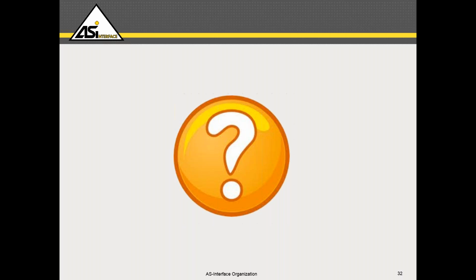Hey John, this is Yen Lee again, I'll take that question. That's really the beauty of the ASI system, right? As a machine builder, you can standardize on your I/O platform no matter if the customer specifies a Siemens PLC, an Allen Bradley PLC, or even a Beckhoff PLC. By doing this, you wouldn't have to redesign your controls architecture every time, and this would save design and engineering time. All it would take to change from one field bus to another is to choose a different ASI gateway. That gateway translates all the ASI information and maps it correctly for the field bus of your choice. From there, it's just data for your PLC to work with. It's really that simple.